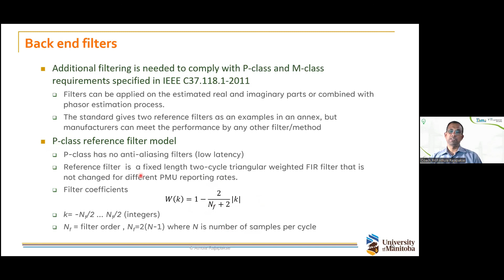At off-nominal frequencies, as mentioned, there are some oscillations going on, so when you do this filtering there will be some error introduced. You multiply your estimate by a certain correction factor depending on the frequency deviation. To compute the frequency, we define it as the rate of change of phase angle. Typically, when computing frequency, you use the most recent samples of the phase angle so you get some sort of average rate of change of phase angle. You can use this formula, which is given in the standard.